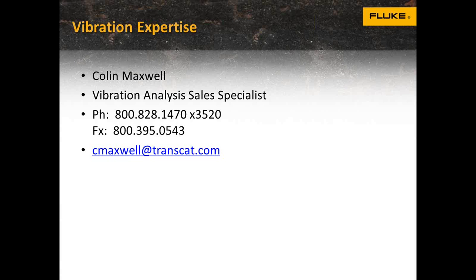The second thing, and this does happen frequently at Transcat, is that we have items that may sit on the shelf for a while. Transcat has the option of doing what is called a stock calibration, which means that we will calibrate it before you get it. If you want that included, you can certainly request it when you request a quote from us.